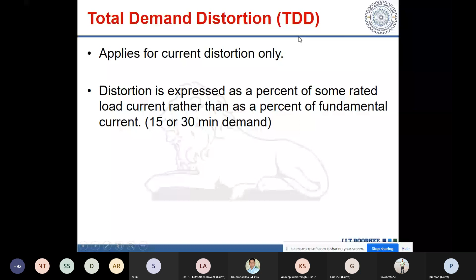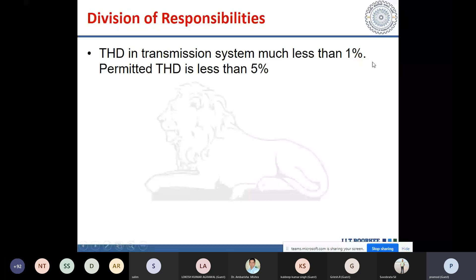And now the question is, if the harmonics are not within the limit, you have to do something so that the harmonics come within the permissible range. Now the question is, who should put something, a filter? Whether the customer should put a filter, or whether the supply authority should put a filter. So, division of responsibilities. THD is very, very less, but permitted THD is less than 5%. The control over the amount of harmonic current injected into the system takes place at the end user. The consumer is basically responsible for injecting harmonic current. The supply authority ensures sinusoidal voltage. The generated voltage is sinusoidal, but the consumer, because of the non-linear load, is responsible for injecting the harmonic current.